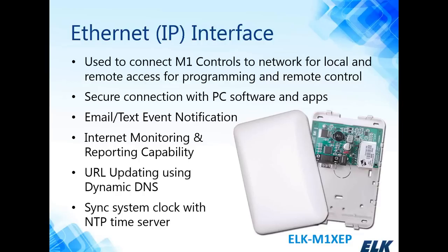XEP, like I said, is used to connect the M1 to the local area network for programming, or it can be accessed through the internet for remote programming. It is a secure connection with the PC and the apps. It uses the secure port and encryption. It also supports email and text notification, internet monitoring and reporting, and URL updating using a dynamic DNS provider. And you can sync the system with a national time server. So the M1 is always within just a few seconds of the national time server. It keeps the date and time up to date.